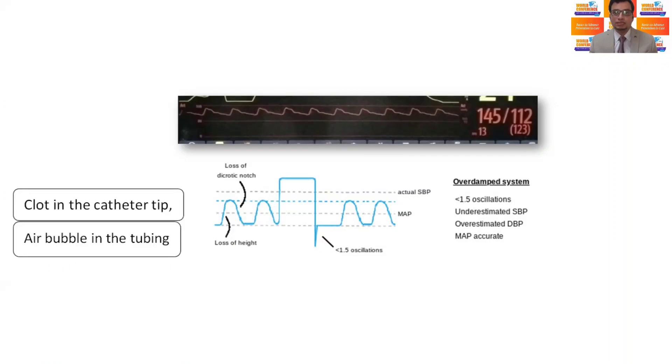The reasons for over-damped waveform commonly seen are air bubbles or blood clots, overly compliant tubing, catheter kinks, stopcocks, no fluid in the flush bag, or low flush bag pressure.